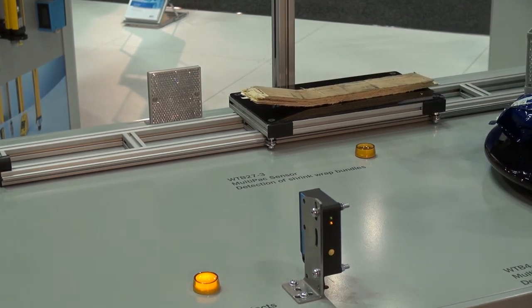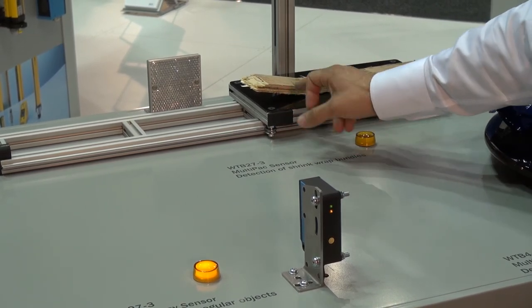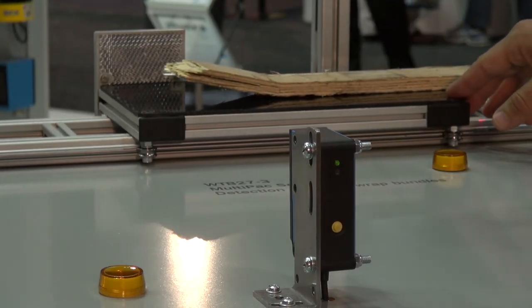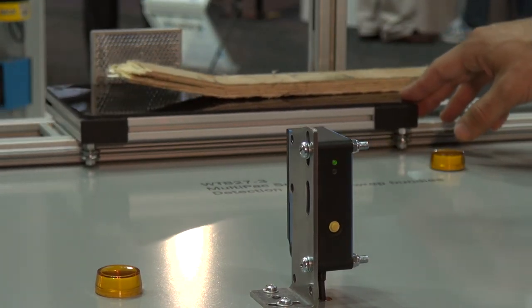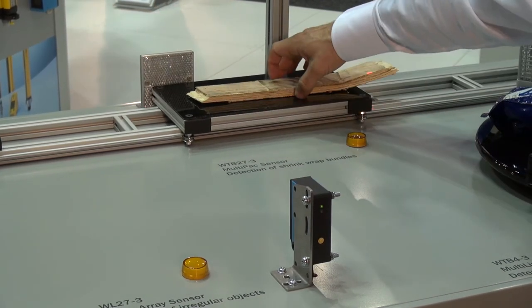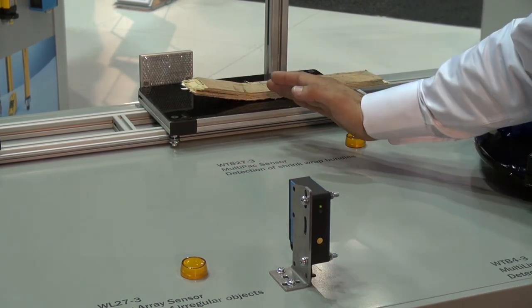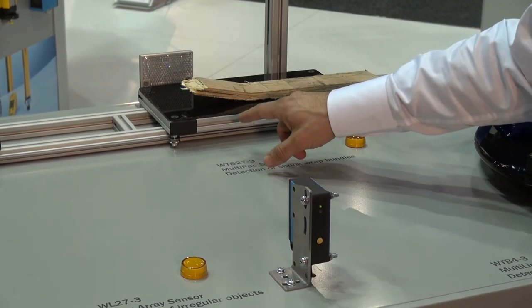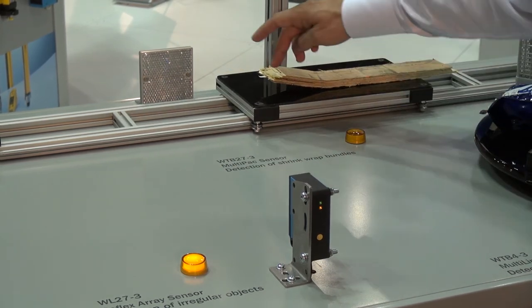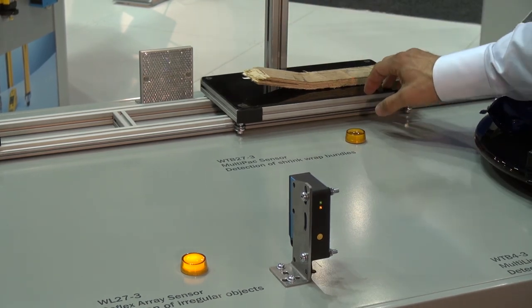Here we're demonstrating an array sensor — if we have an object which is damaged perhaps, or has an edge which is lifted above the datum point which would be the conveyor, we're still detecting the leading edge with the array sensor. Typically the object would be flat, but quite often we have pallets or objects which have rising edges, and a typical sensor would look underneath that and we wouldn't have a detection. With the array sensor we pick up the leading edge and we have a very secure leading edge switch point every time.